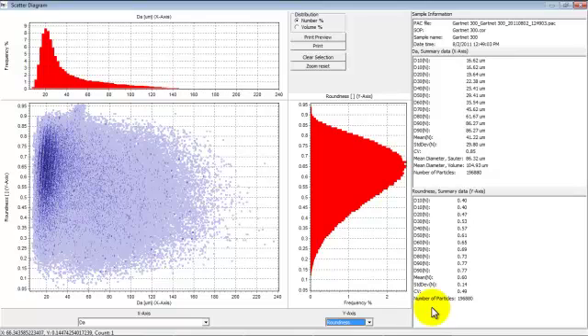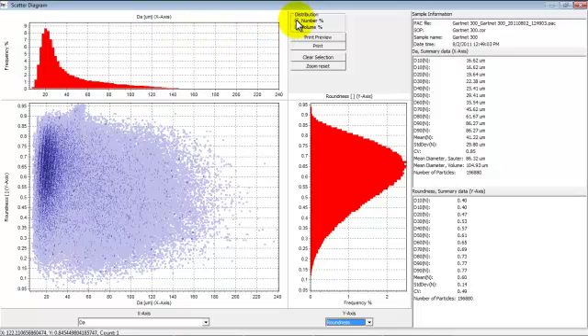Here for the x-axis, and here for the y-axis. On the right are long lists of summary data for each of the two parameters plotted on the x- and y-axis. Currently, the area equivalent diameter is on the x-axis and circularity, a shape factor, is on the y-axis. The area equivalent diameter, dA, is displayed as a number distribution here. And we can see the d50 value change from 29 to 106 microns when it's changed to a volume distribution.